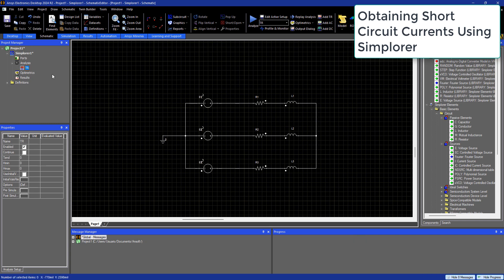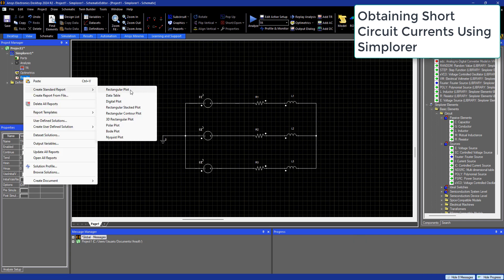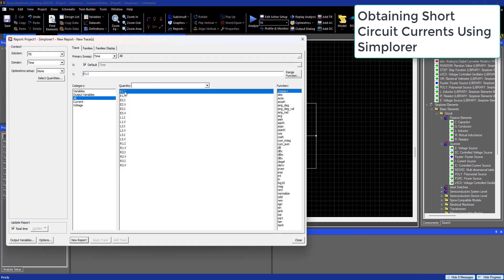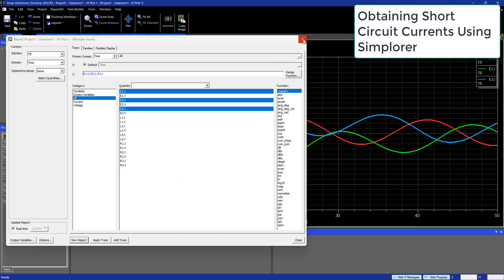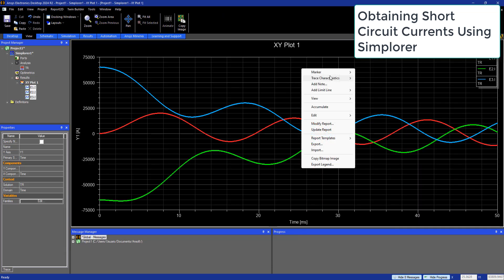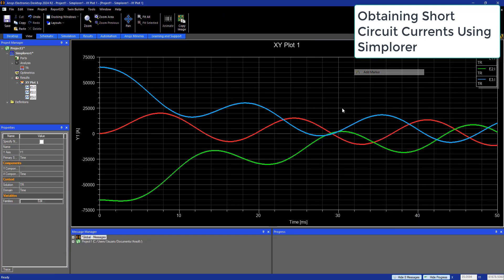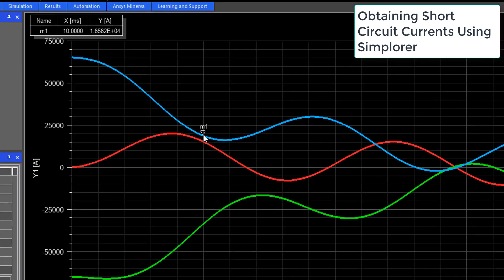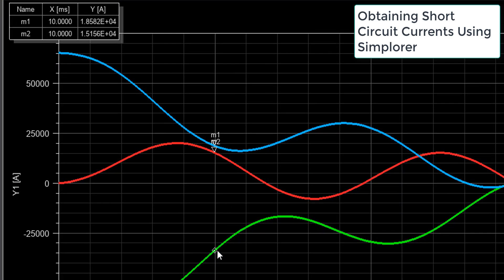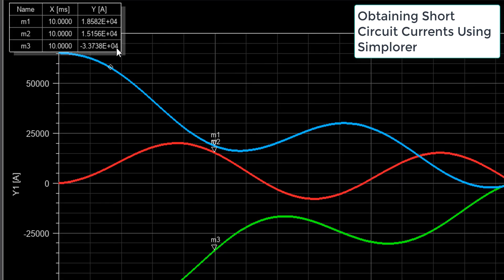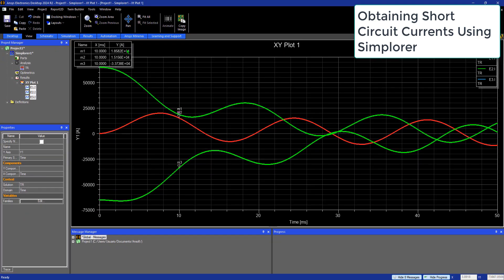Currents are pretty high, so we will select the values at 10 milliseconds and simplify them to 20 kilo-amps for the two high side busbars and 40 kilo-amps negative for the remaining busbar.